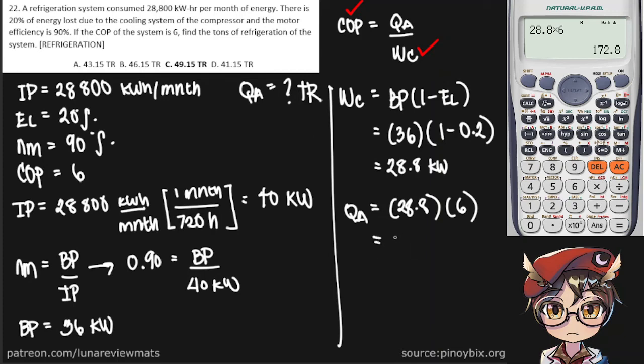172.8 kilowatts. Now, if you remember, there are 3.52 kilowatts per ton of refrigeration. So all we need to do to convert this into tons of refrigerant is divide by 3.52. And that gives us an answer of 49.1 tons of refrigerant. And that is our final answer.